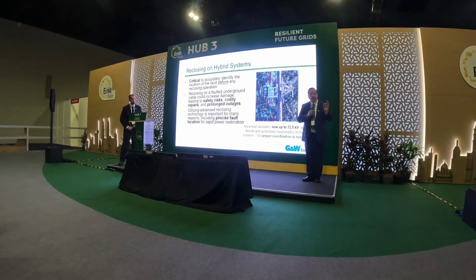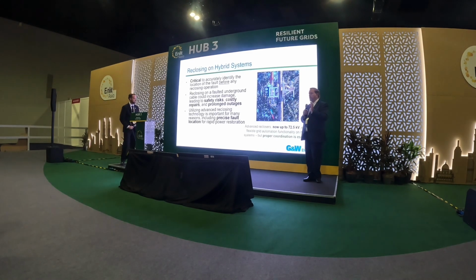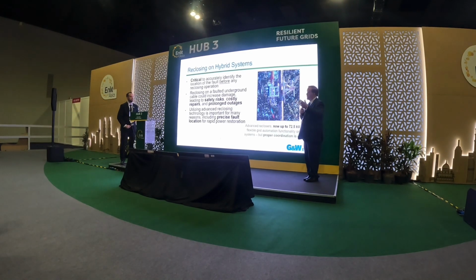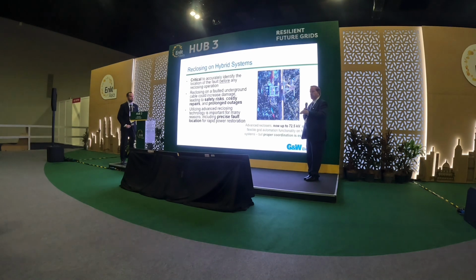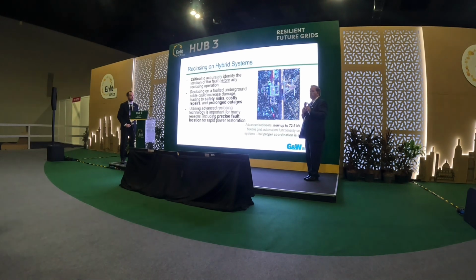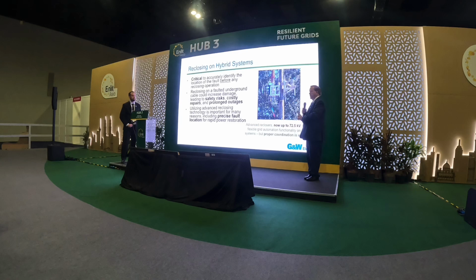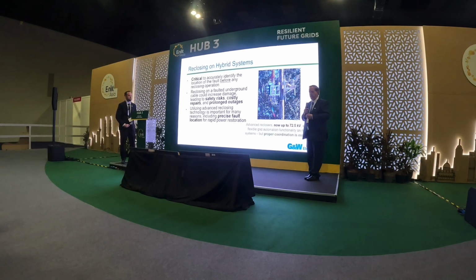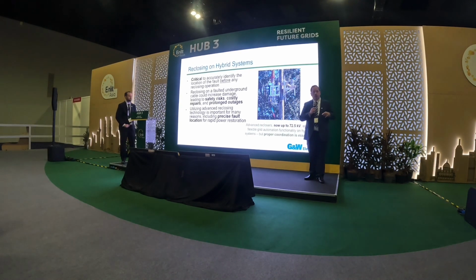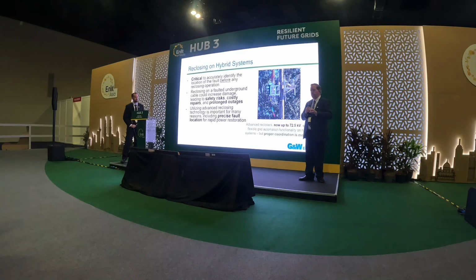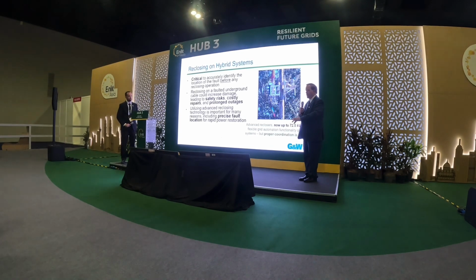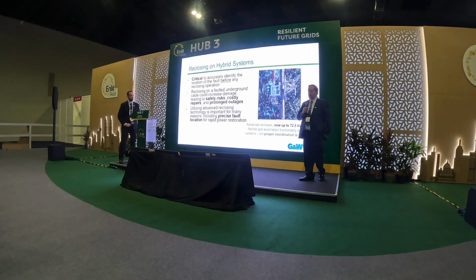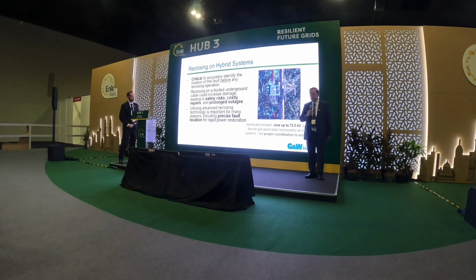So what is really, really important, and this requires coordination in your system, is that before you reclose, you need to know where is the location of the fault, and there are ways to determine that. Because if you do reclose on that underground cable and it's a bolted fault, a permanent fault, really bad things can happen, depending on the amount of energy that is pushed through that system.